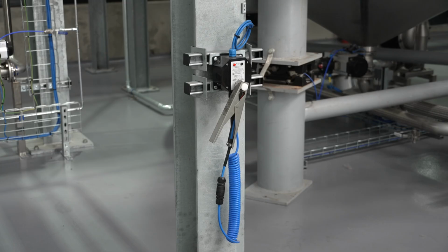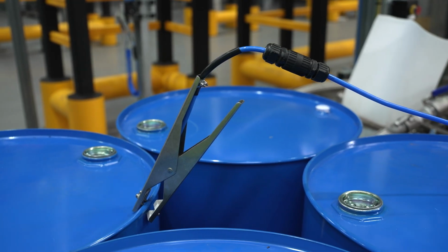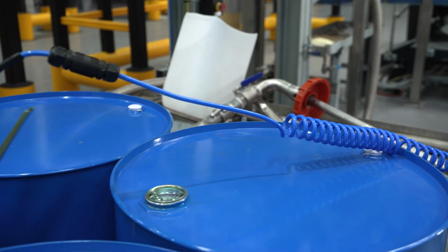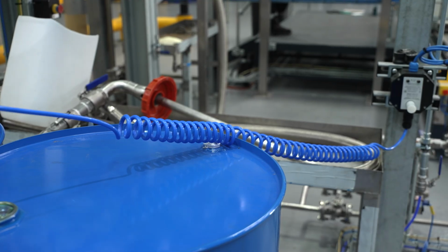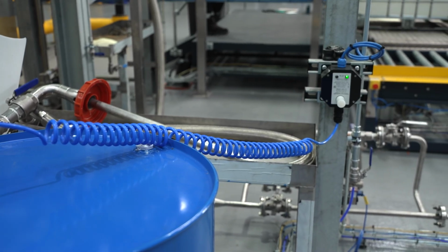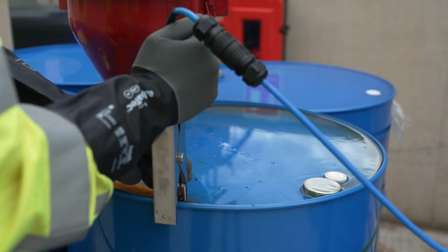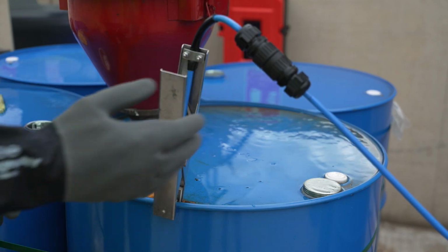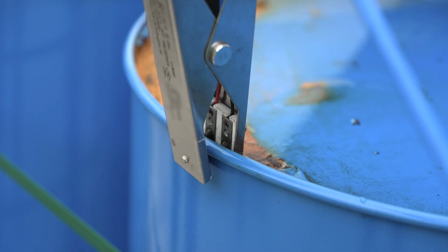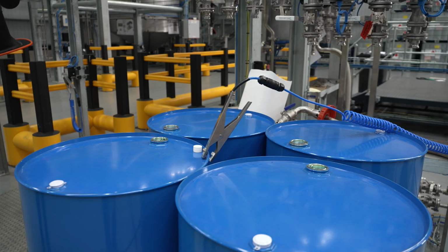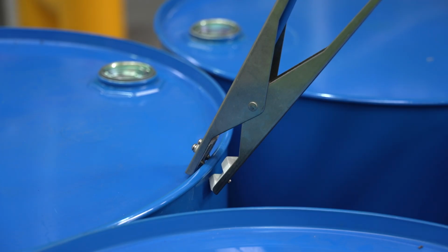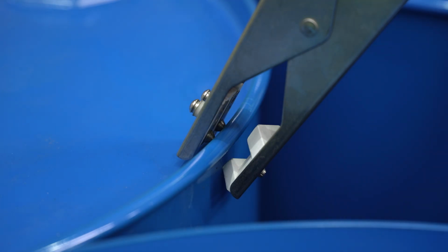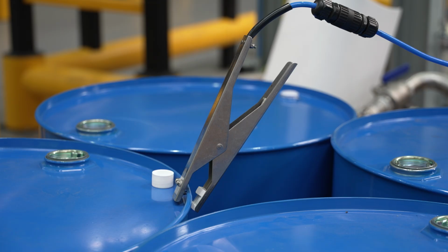Bonding straps and cables should be durable and have a low resistance of less than 10 ohms. Portable equipment must be earthed back to a known earth reference point or common earthing system using the appropriate flexible cables and clamps. The clamp must make contact with metal surfaces through paint, rust and surface contaminants to achieve a connection of less than 10 ohms. Metal containers must be earthed back to the loading system via earth leads and a suitable earthing clamp that penetrates the paint coating. Ensure that both containers are suitably earthed when decanting from one to another.